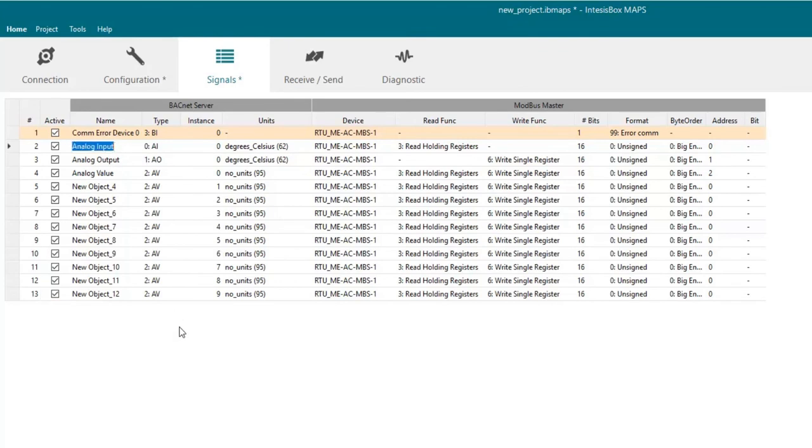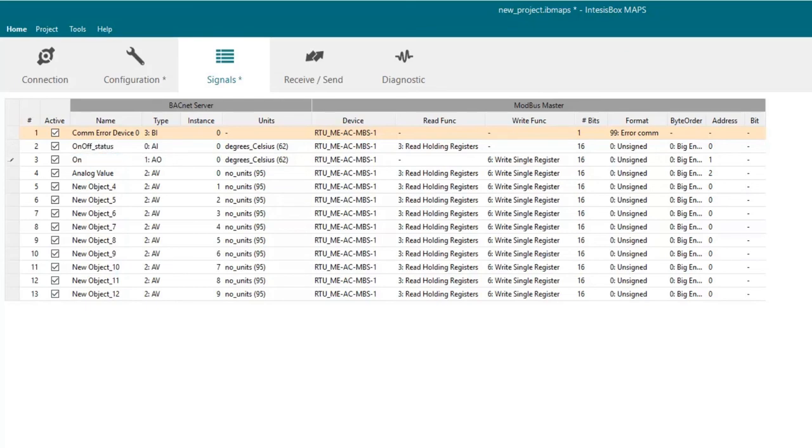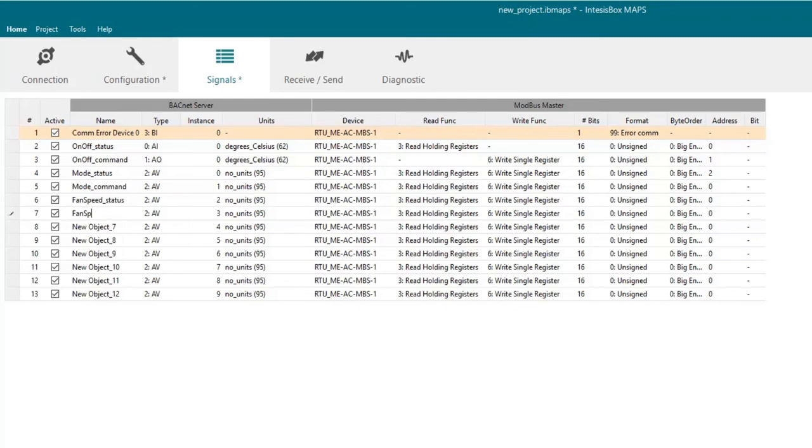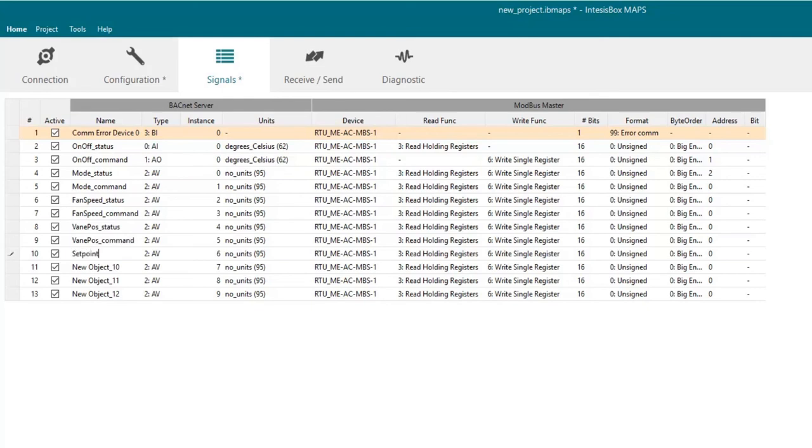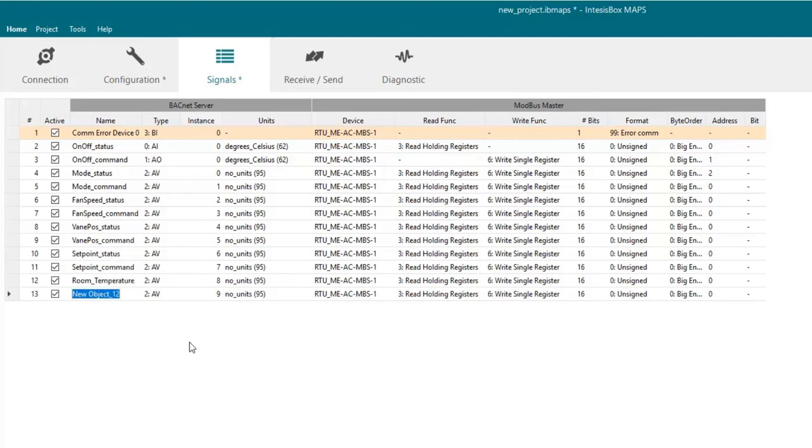Now we are going to give the names of the signals we want to integrate. They will be on-off status and on-off command, mode status and mode command, fan speed status and fan speed command, vane position status and vane position command, set point status and set point command, room temperature and finally error code.